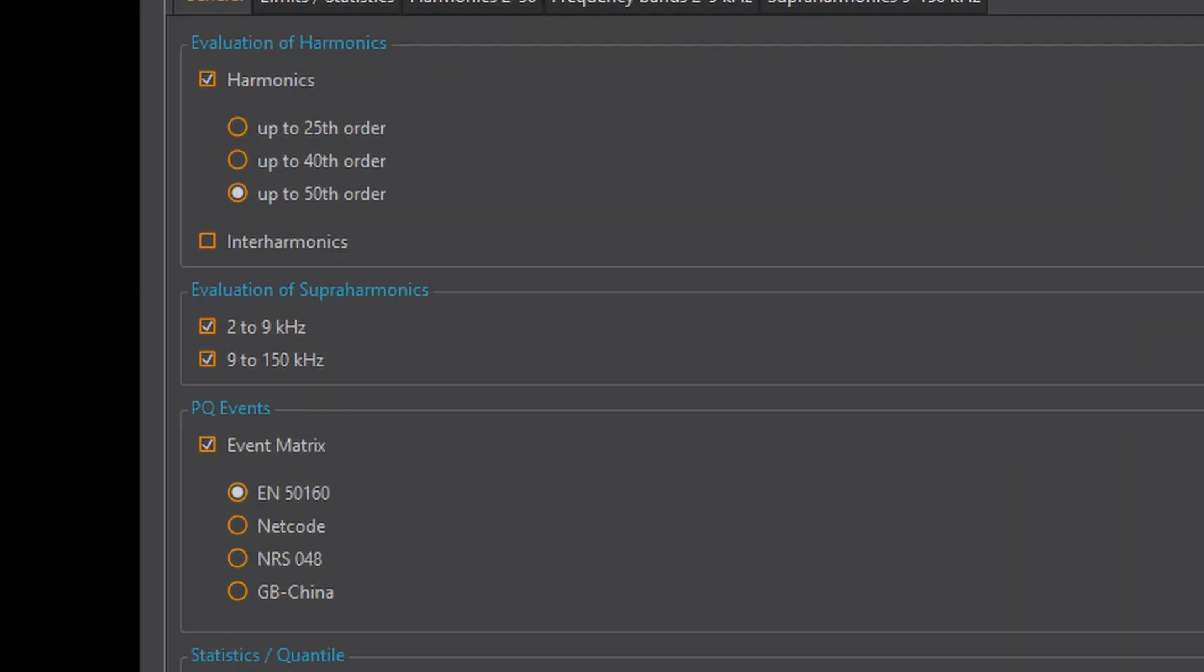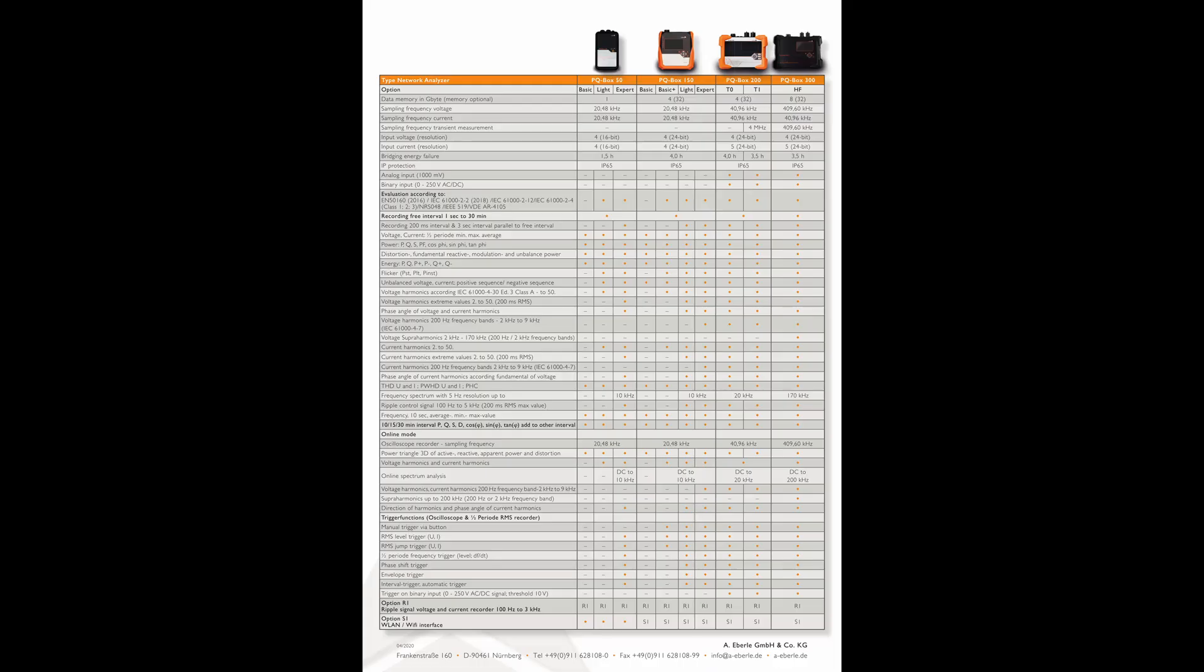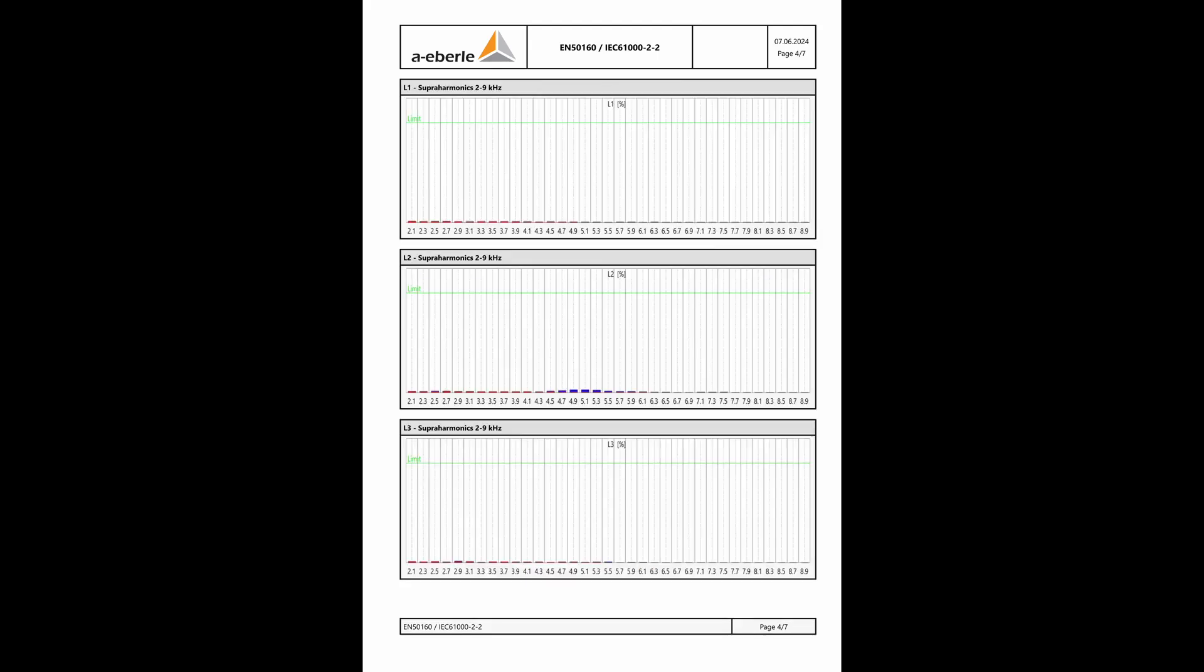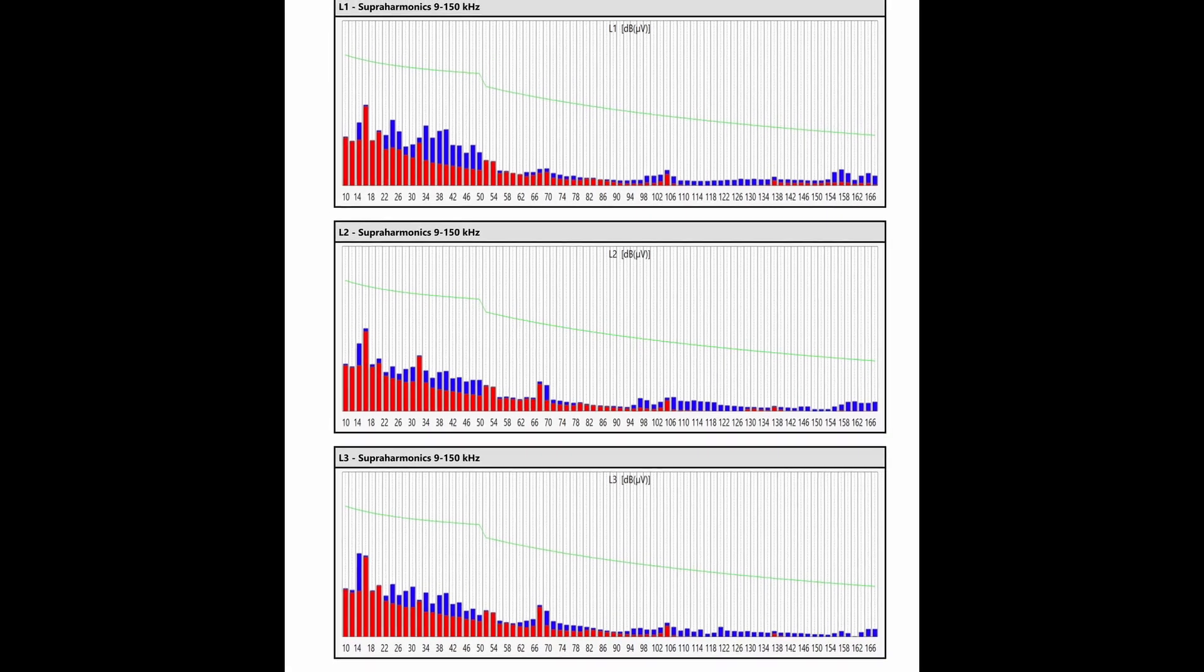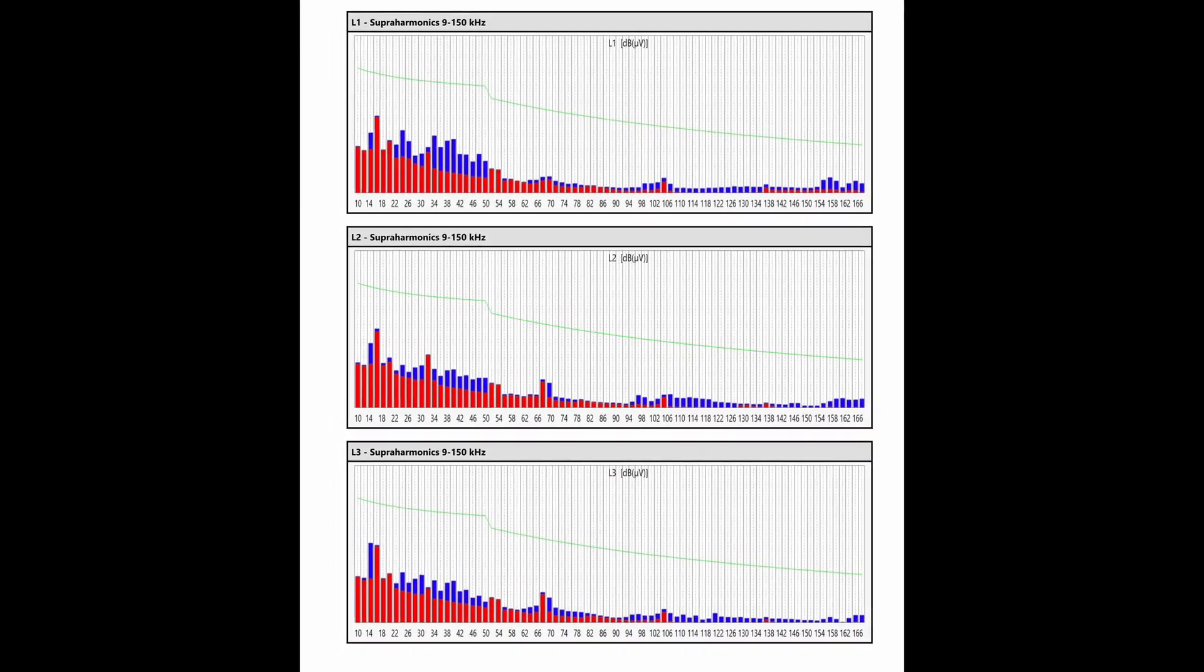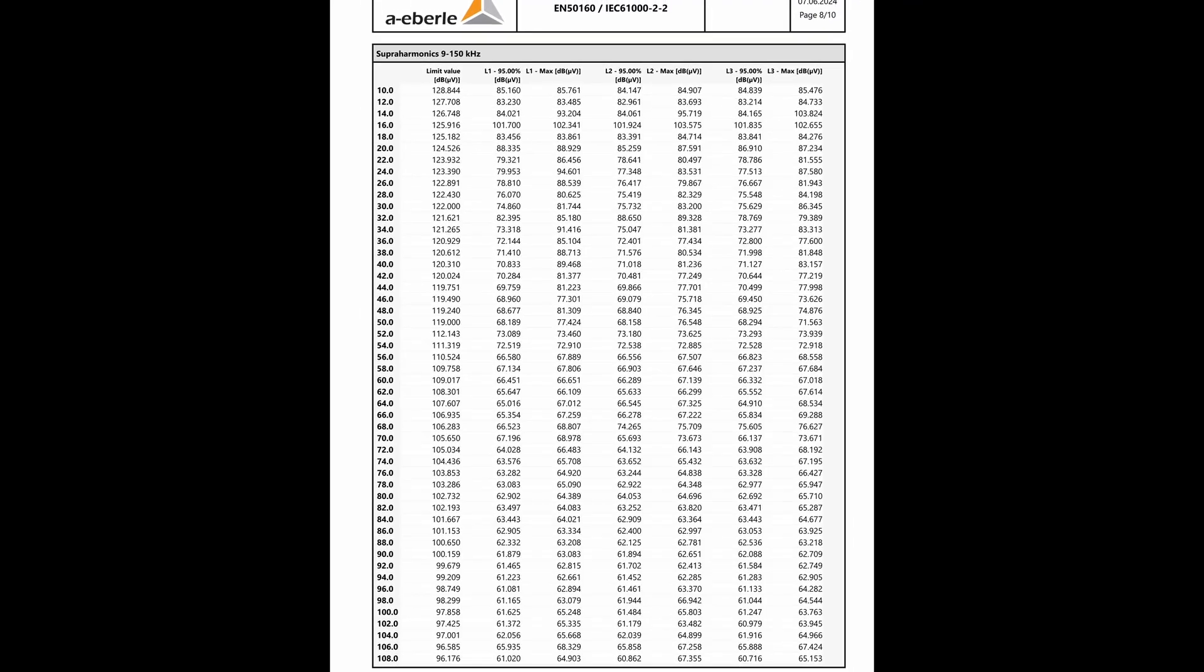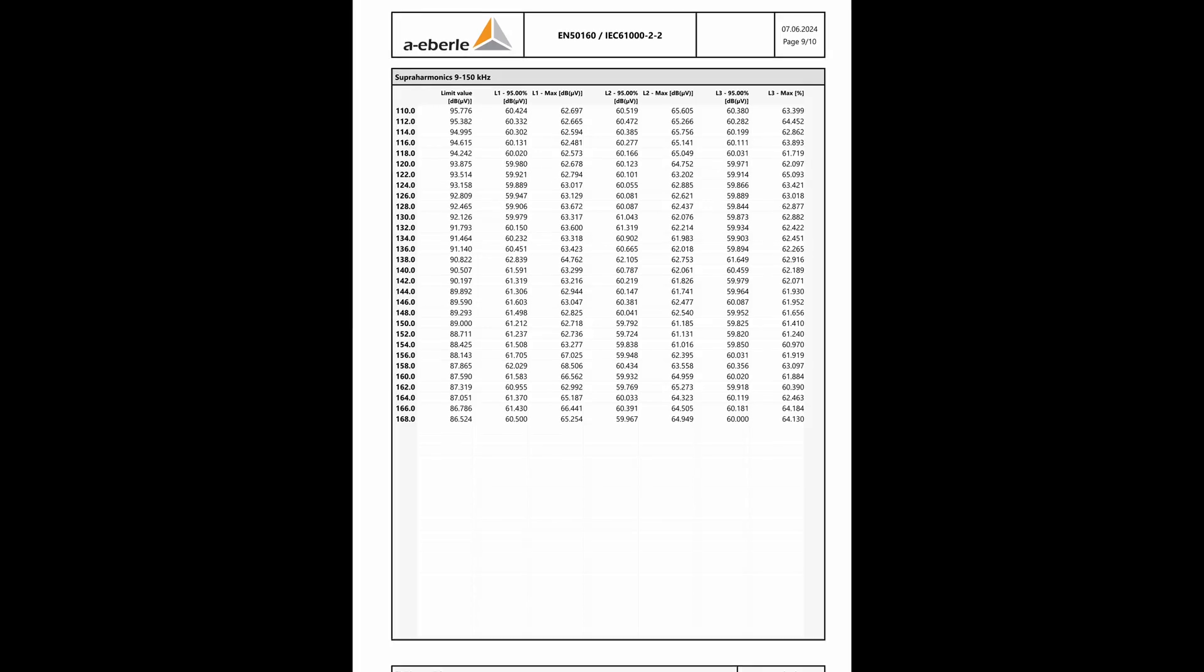The measurement of supraharmonics from 2kHz to 9kHz is only possible from the PQBOX 150 expert onwards. Consequently only then will the evaluation be displayed in the report. An additional category supraharmonics appears in the overview and the data is displayed graphically and in tabular form from page 4. The supraharmonics from 9 to 150 kHz from a PQBOX 300 can also be found in the report following the same pattern.